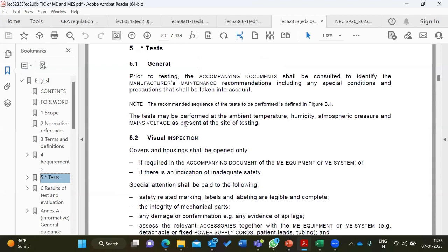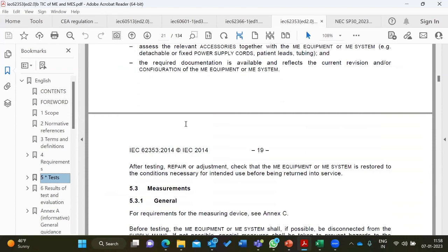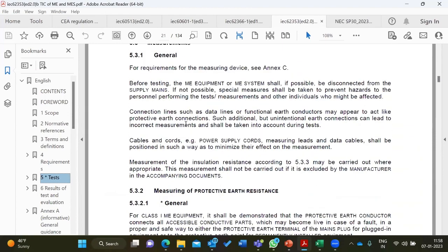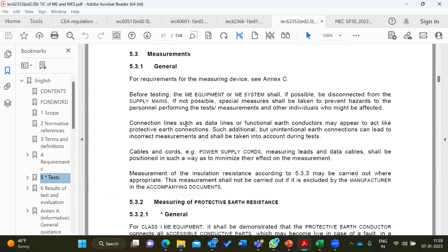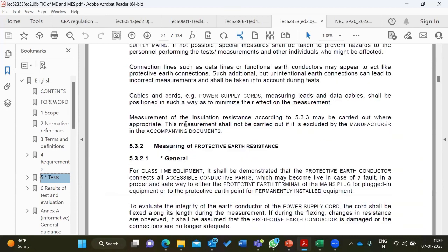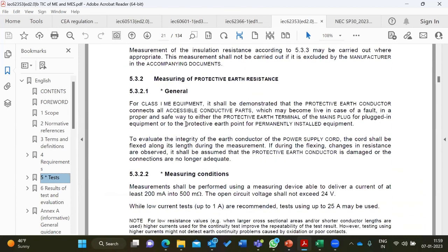I'm just showing some of the requirements. For example, the first test, of course, is visual verification, then the actual test. For example, clause 5.3.1, measurements 5.3.2. The first measurement is the measuring of protective earth resistance, the most important subject for class 1 medical equipment. In class 1 medical equipment, I have a metal body which can experience a voltage which can be fatal.